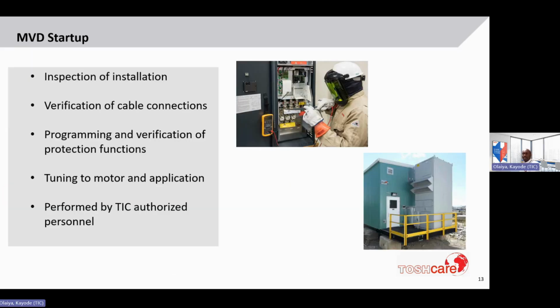So part of the advantage of a proper startup is to catch some of these things during the beginning of the drive operation. Proper inspection of the installation, making sure the drive is installed properly, making sure the cables are connected in the right locations, making sure they're secure and tight, making sure the programming is correct, the protective functions are working, and then the drive is tuned for the correct motor that's connected to it and the application, so that ultimately the drive performance will be maximized because it has been set up correctly. All these steps are best when done by TIC authorized personnel to make sure that you're getting the best out of the startup.